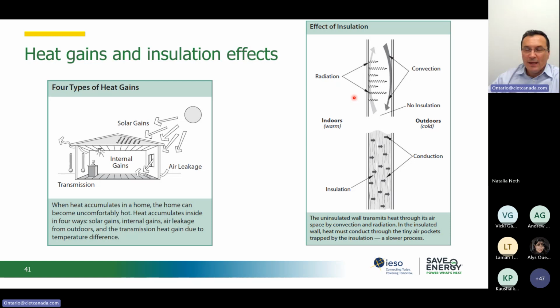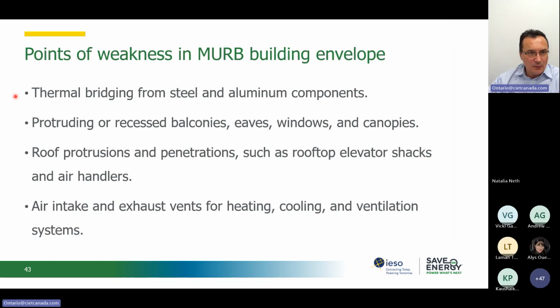So if you look at where these weaknesses are in our building envelope, we have thermal bridges that are created by the structural elements in our buildings. Steel, aluminum components, concrete are structural components of our buildings that create these thermal bridges. We may have the geometry of the building with balconies, different shapes of the buildings that increase this exposure of the structural elements to the outside, and therefore present an opportunity for the heat to flow freely through these thermal bridges. Roof protrusions and different penetrations we have for mechanical systems can increase this heat transfer as well.